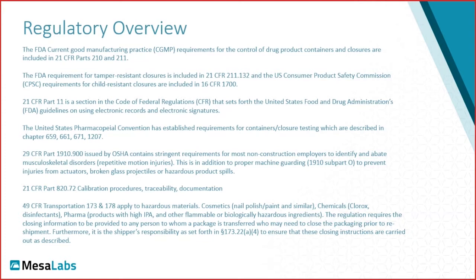In 21 CFR Part 820.72, there are details about how torque testers, or any device basically, should be calibrated, and how often: the frequency, traceability, and documentation requirements. And finally, I wanted to mention that there's also a transportation regulation in 49 CFR Parts 173 and 178. Those apply to hazardous materials.